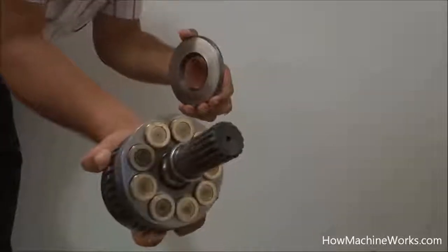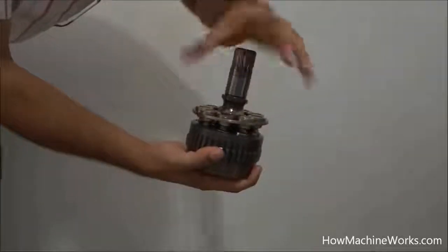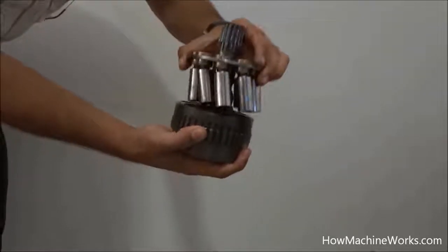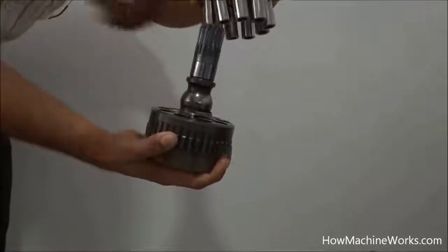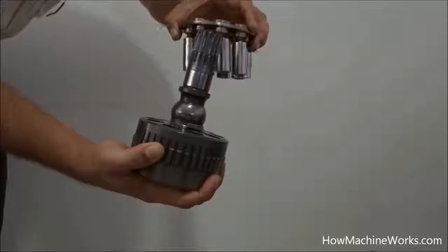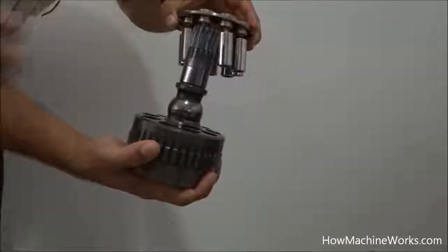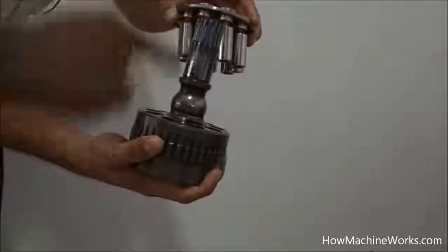So I already showed the rear view over there, and that's actually resting on the swash plate. Now let's remove the pistons outside. So those are the pistons being taken out, and the o-ring has gone down, I think. Okay, we have the pistons over there. We have many pistons which are inserted into the drilled holes inside the cylinder. You can see the shaft and the cylinder is a single piece over there. The drive shaft is directly connected to the cylinder at that section.